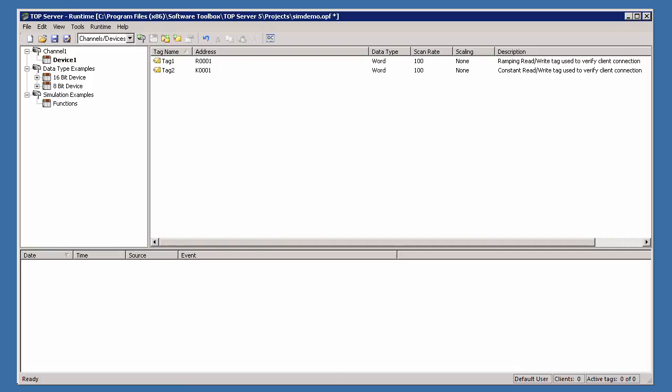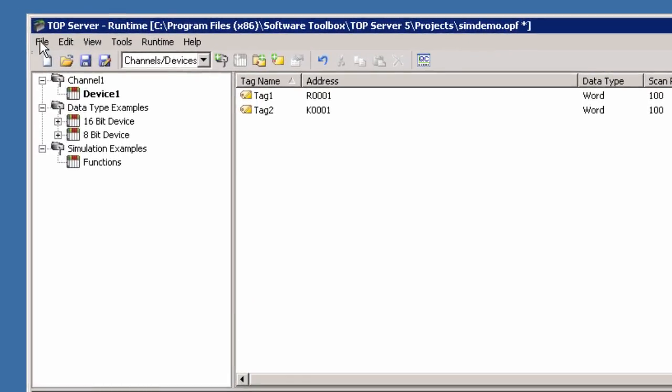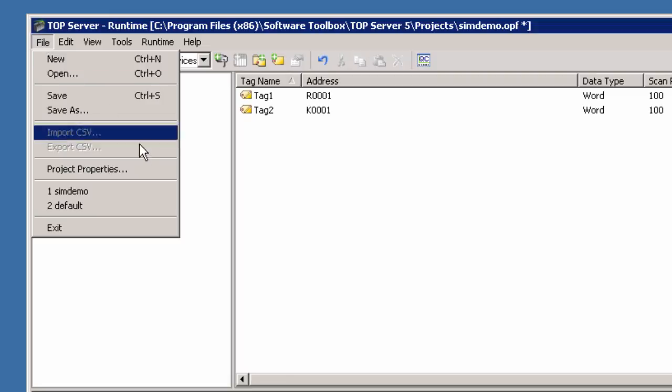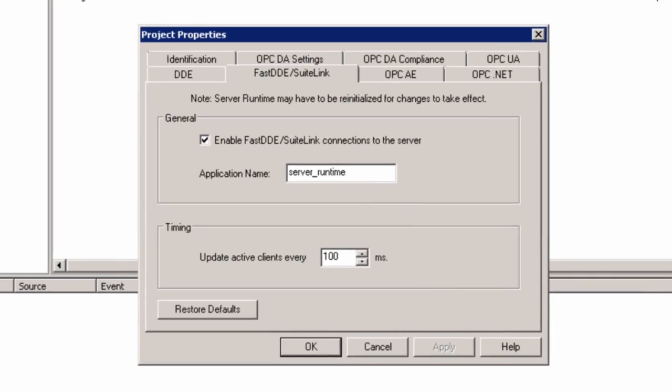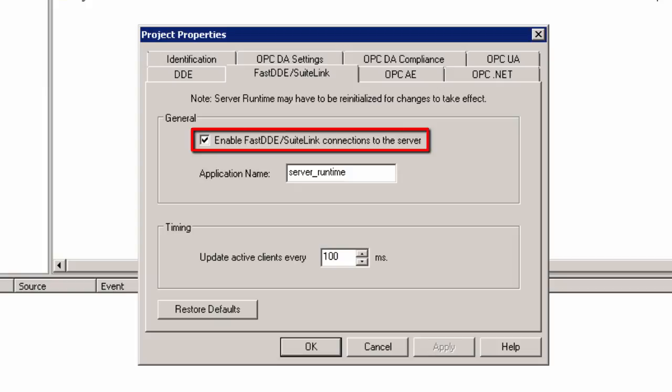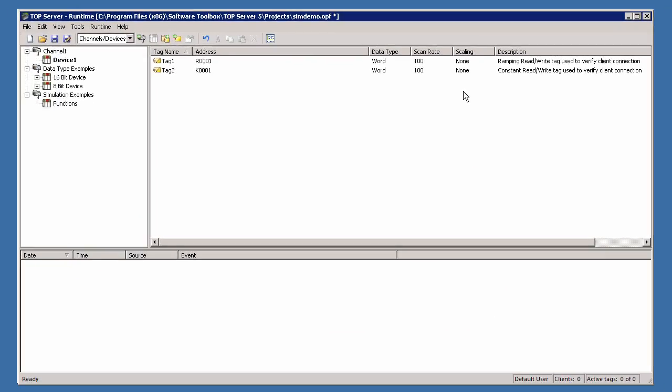Once the TopServer is successfully installed, we will launch the configuration window and check to make sure the SuiteLink interface installed properly. To do this, click File Project Properties and navigate to the FastDDE SuiteLink tab. Make sure FastDDE SuiteLink connections to the server are enabled. If you do not see this tab in the Project Properties, you will need to go back and ensure the Native Client Interface and Wonderware common components were installed successfully.